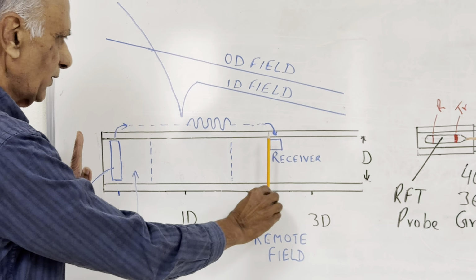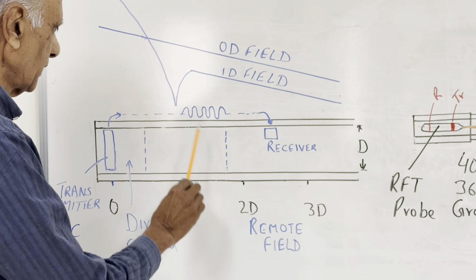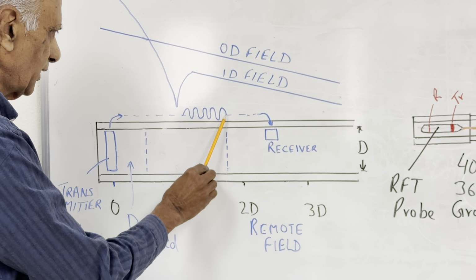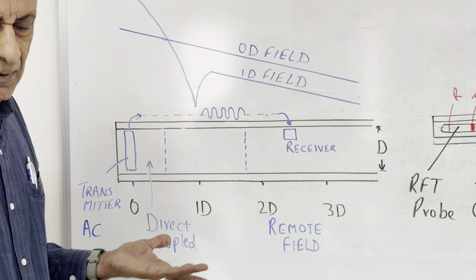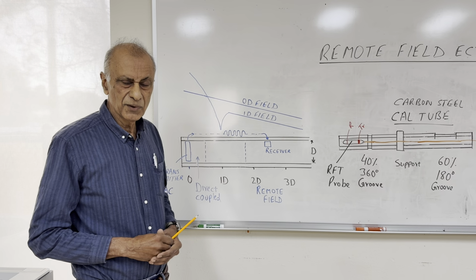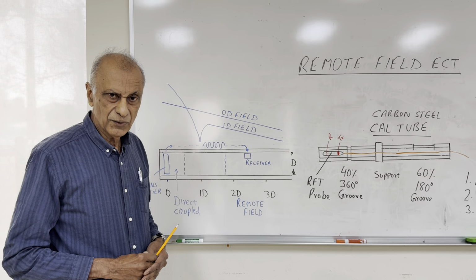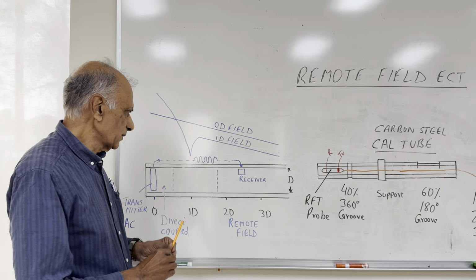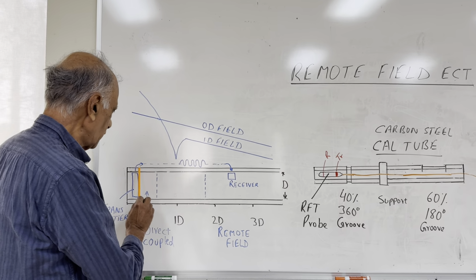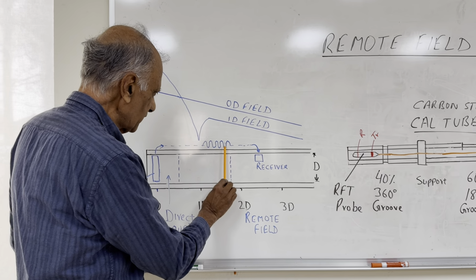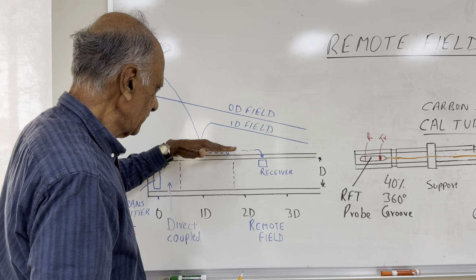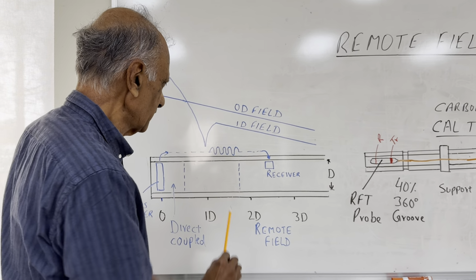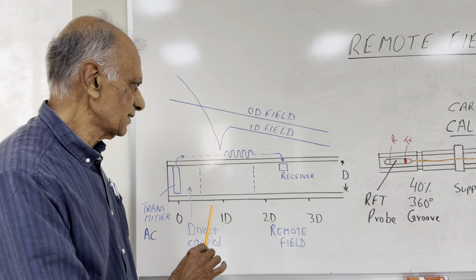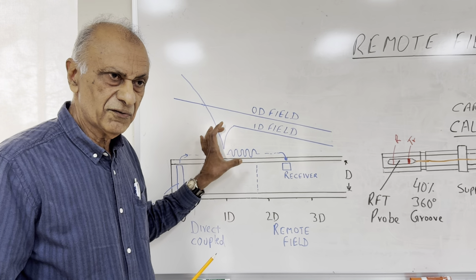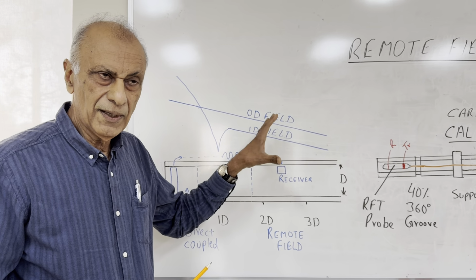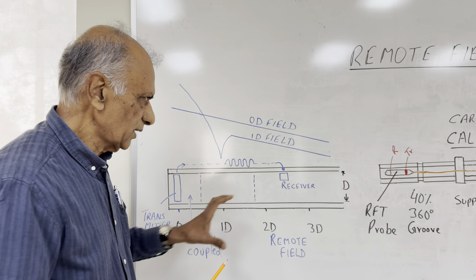So the transmitter and receiver are separated from each other. There is a signal which goes from the transmitter, which is a continuous signal here, and it's about, let's say, 400 hertz when we are inspecting a tube which is 3/4 inch by 0.083 inch thickness. And so when there is wall loss here, this phase of this signal will shift, or there will be a time change in this signal, and that's called the phase shift of the signal. And we plot that phase shift on the instrument using a polar plot, which I will show you on the other side.